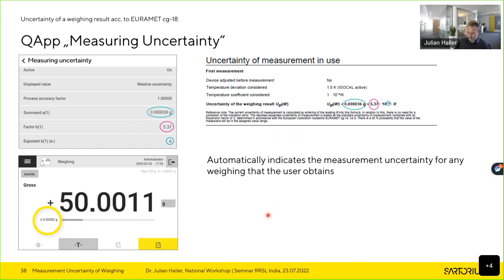Now, let me finish with a last part, the so-called minimum net weight according to Euramet CG18, because that is based on the previously shown measurement uncertainty determination. This is a slide we've seen before. Again, this is how the straight line equation for the expanded uncertainty over the weighing range is determined. So if you have a look at the absolute uncertainty in grams or milligrams over the weighing range of a weighing instrument, it's just a straight line. But if you take a look at the relative measurement uncertainty, so you divide each value by the respective load to get a relative uncertainty in percent, then it will automatically be a so-called hyperbola. And that means, you see it directly here, the relative uncertainty increases to infinity for small loads.